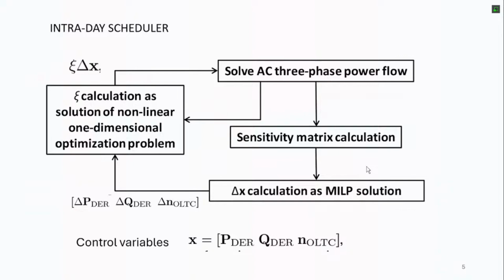So what is the sensitivity matrix? There is also a slide for that. It is the sensitivity of what we need to control, for example the voltage, with respect to the injection of active or reactive power, so variation of the active and reactive power in the various nodes, or the change in the tap changers. So how does the voltage vary in bus i when the injection of active and reactive power in bus j is varied by a small change, a small delta?